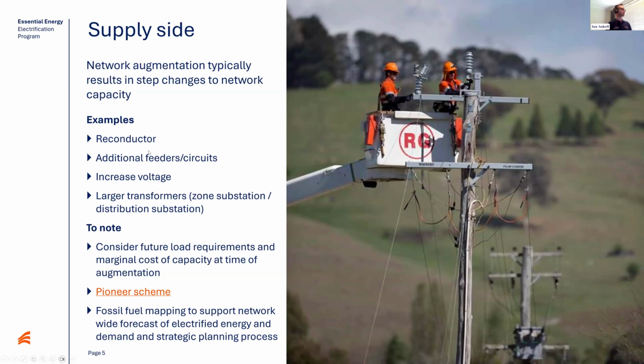Examples include reconductoring with bigger size conductor, adding additional circuits or feeders, or increasing the voltage - say doubling it to double the power through the same line - or installing larger transformers. One thing to note is that augmentation of the network, physically reconductoring or increasing a transformer, typically involves step changes in capacity.